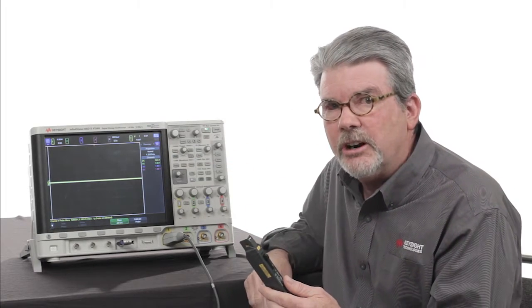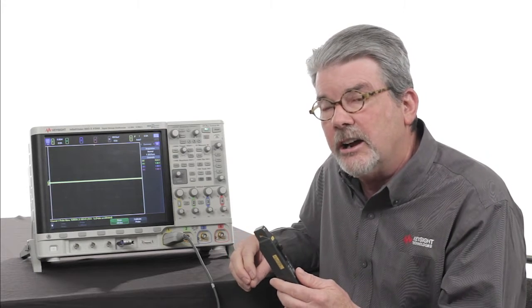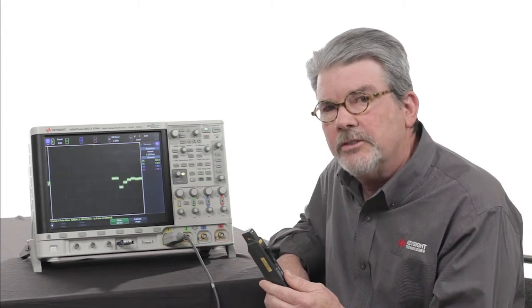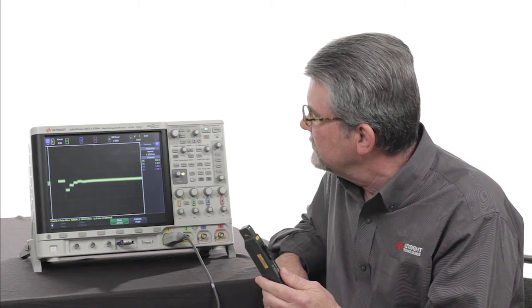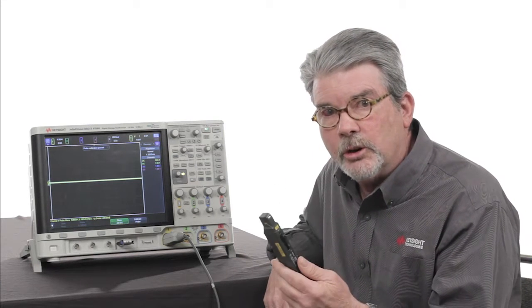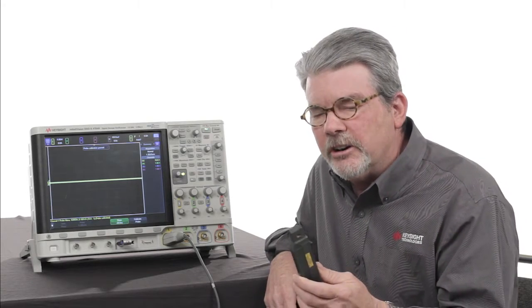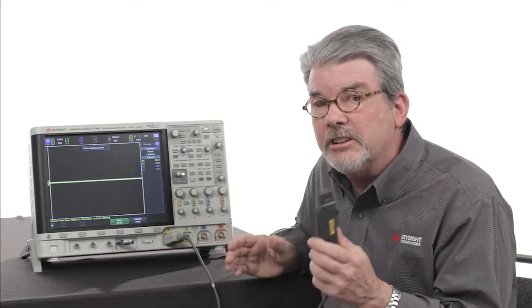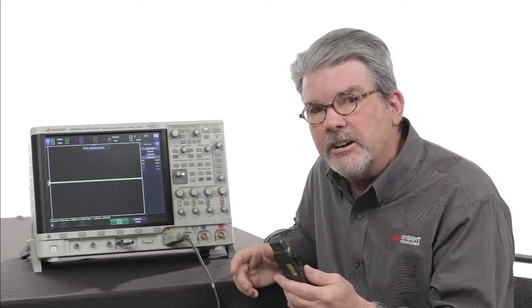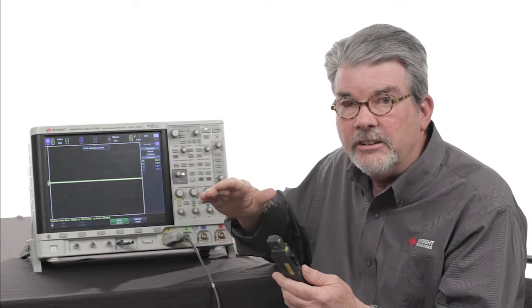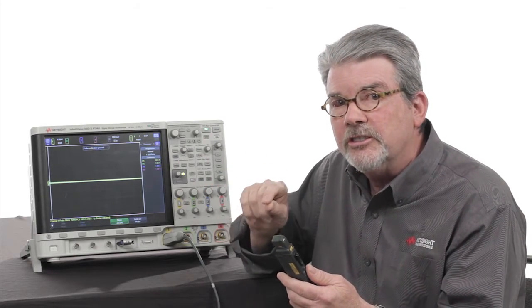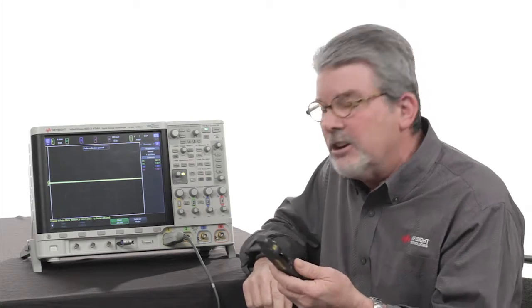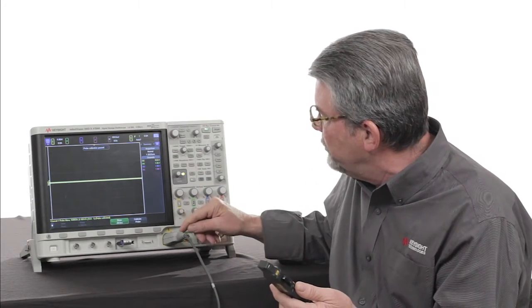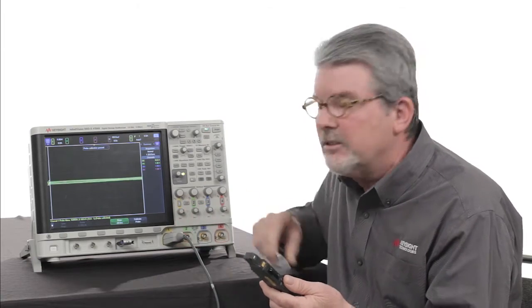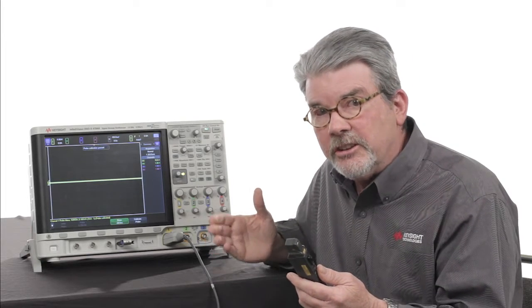And then there's a slight pause, and then it's going to do an automatic offset calibration. This is the offset calibration. Now at this point, our probe is calibrated. But something you should be aware of is you do need to occasionally degauss the probe. It can build up a magnetic field which will cause a DC offset. There are ways we can remove the DC offset in the measurements, and we'll show that in a few minutes. But if you just want to occasionally degauss the probe, there's a button on the probe. Just press the button and it will degauss. You really don't need to perform a new calibration, which includes the offset measurement.